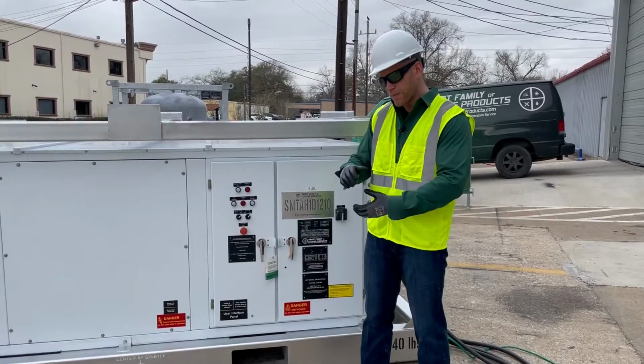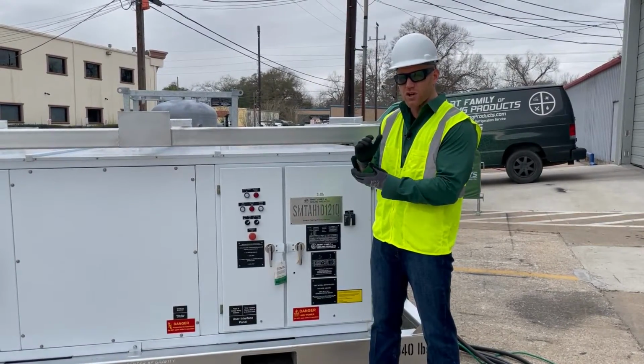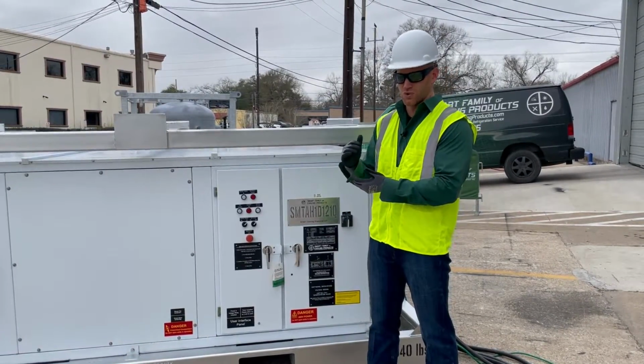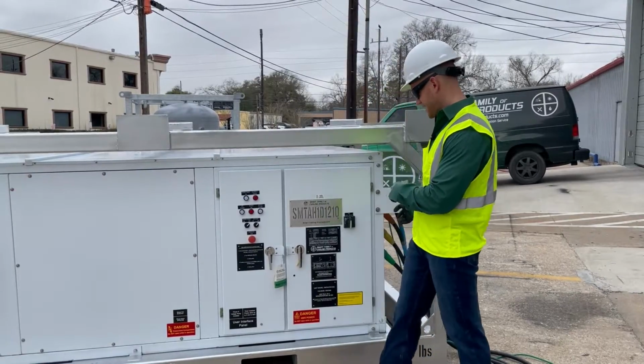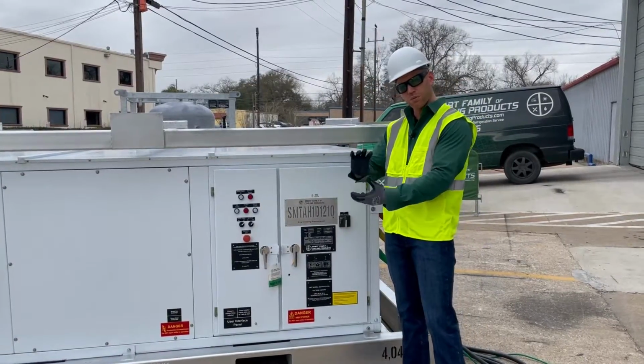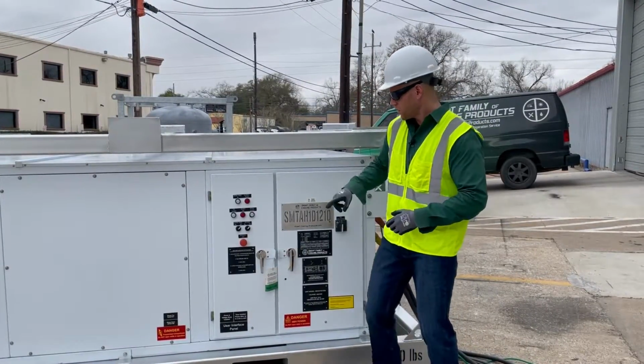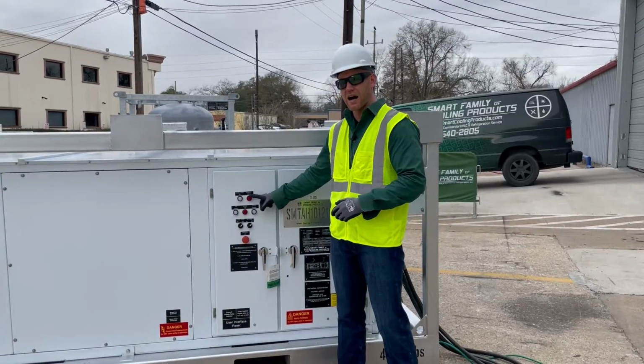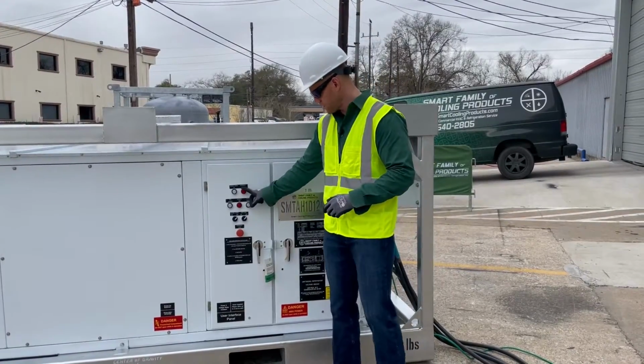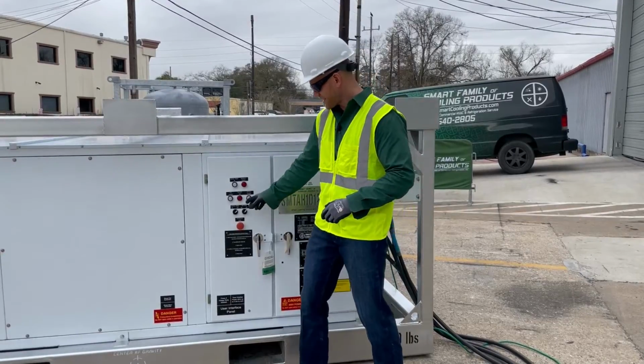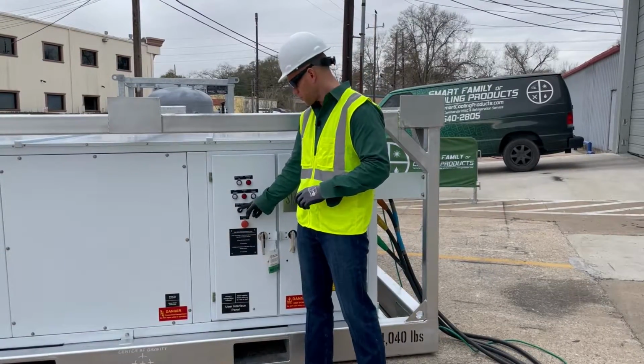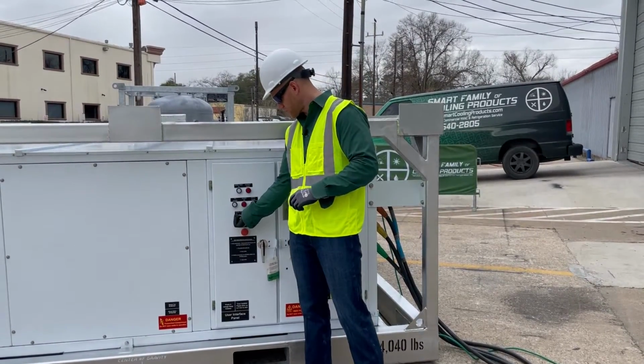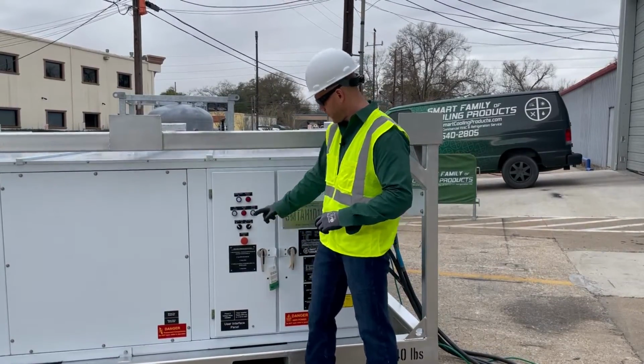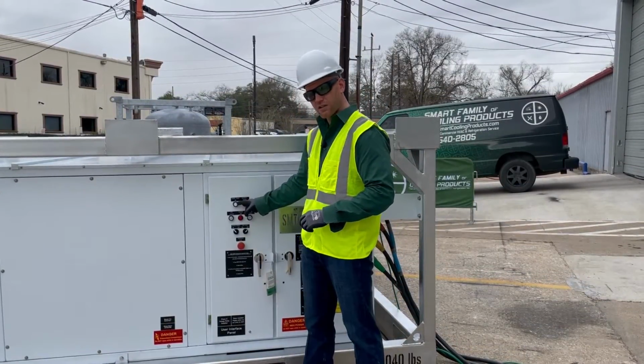Please be mindful that the phase monitor is also an over and under voltage relay monitor. So if you don't give the exact power that this machine is asking for, plus or minus some tolerance, the incorrect power light will remain on. So you need to give good, correct power to the unit. Now I'm ready to go ahead and grant this unit 110 volt control power to all the controls. So I'm going to turn my control power switch to on. You'll see immediately I get a control power light.